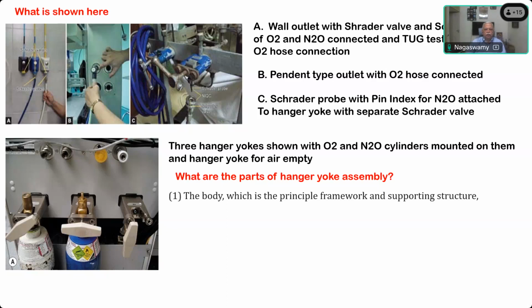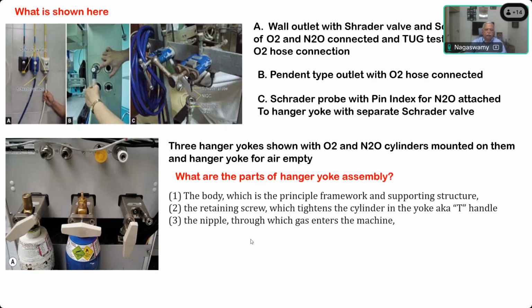So the body is the principal framework of the yoke assembly, and this is the one which is supporting the entire weight of the cylinder. The retaining screw is the one which tightens the cylinder to the yoke, also known as the T handle. This white thing is called the T handle. The third is the nipple through which the gases go. This is the entry port or nipple through which the gas enters the machine. And there are 2 index pins, below the nipple port through which the gases go, which prevent attaching an incorrect cylinder.